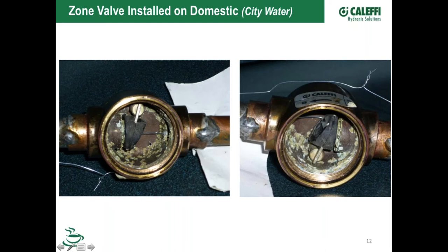The flapper didn't have a buildup on it when it's open, but it was still closing off. It got sent back to us, and they said, well, is this something coming out of your brass? Is your brass breaking down here? Is this a defect or a flaw in your component? And of course, no, the answer is it's you. It's the water you've been putting through there, and probably the temperature of the water going through there that causes those minerals to precipitate out.